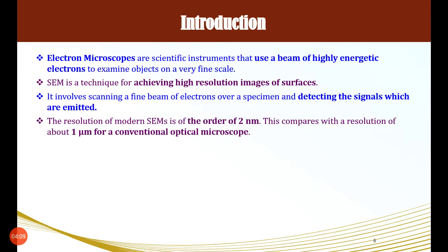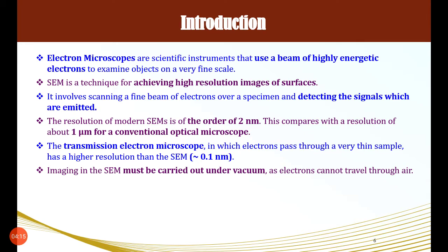By using a conventional optical microscope we can see up to only 1 micrometer, and by using TEM we can see up to 0.1 nanometer. The imaging of SEM must be carried out in vacuum because we use a highly energetic electron beam. Electrons would ionize any air or gas particles present, therefore the whole system is placed in high vacuum. Note: 1 nanometer means 10 raise to minus 9 meters, and 1 micrometer means 10 raise to minus 6 meters.